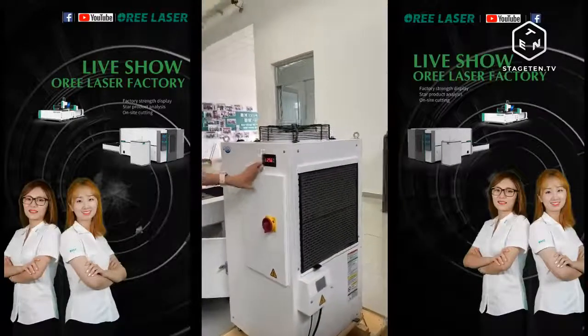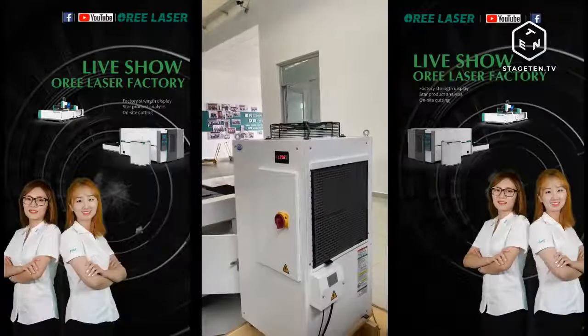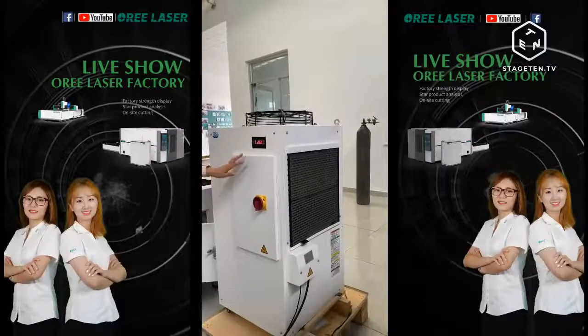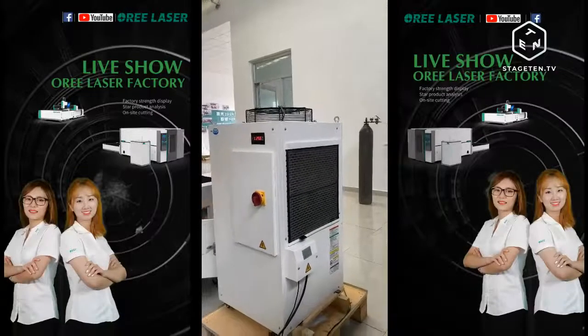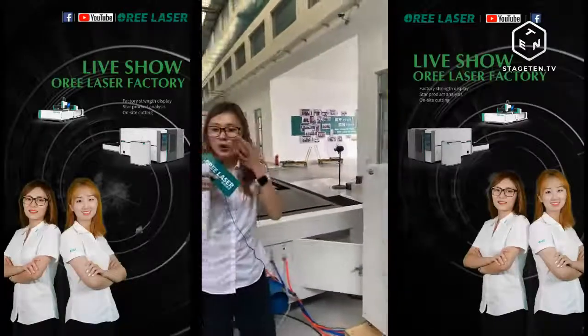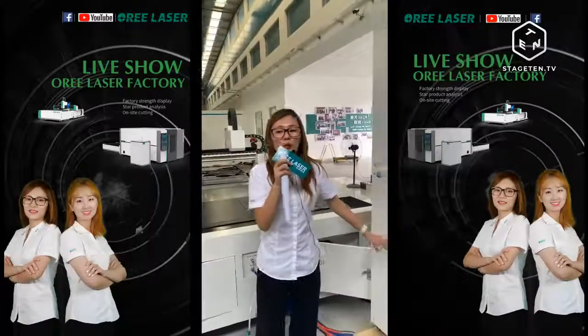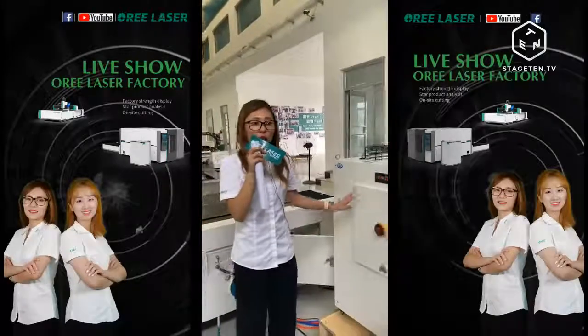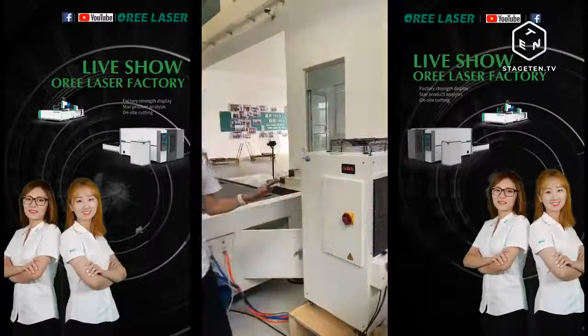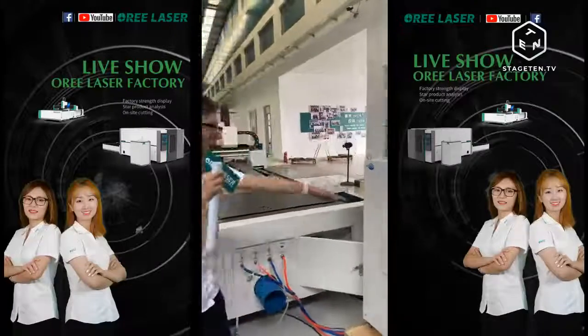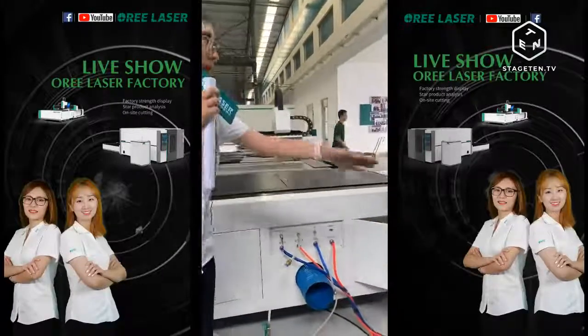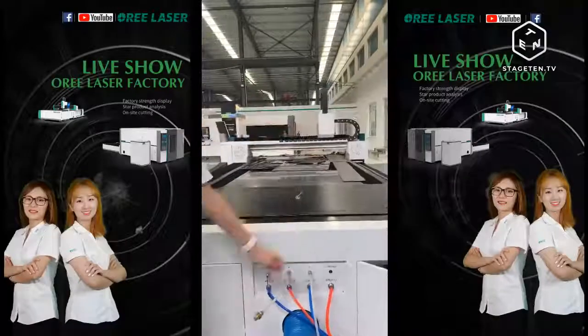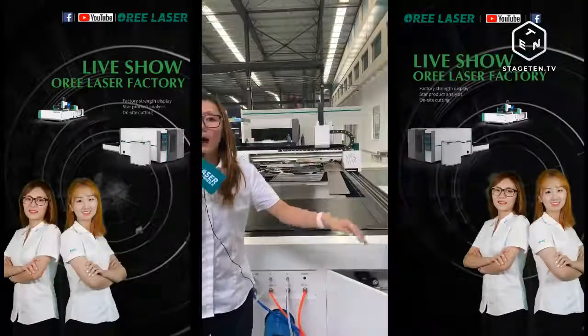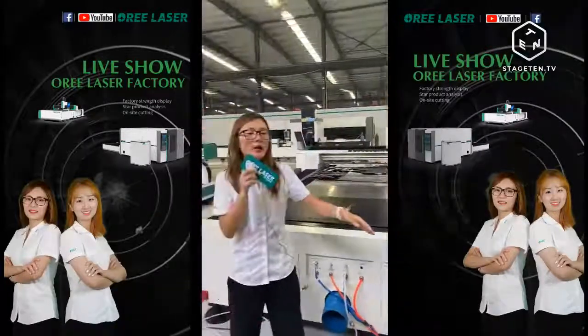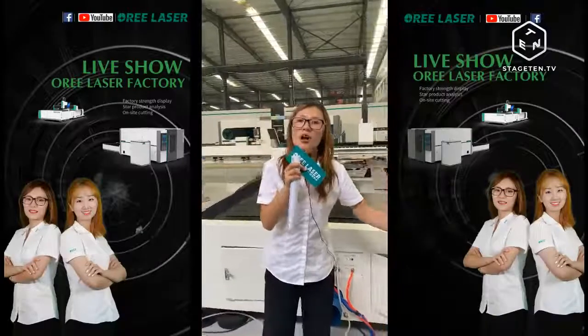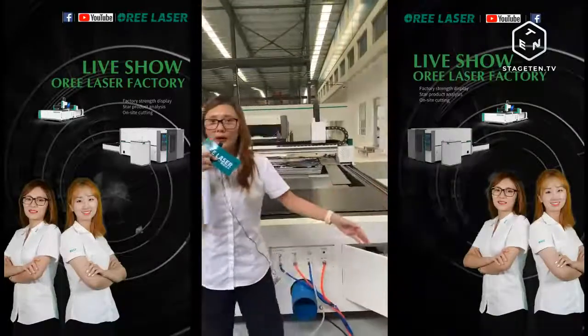The low temperature water way is about 20 to 25 degrees, and it cools the laser source. The high temperature water way is 25 to 30 degrees, and it cools the laser head. There we connect the air pump to the laser head, so with constant temperature it will always keep the laser source and laser head in the best working condition.